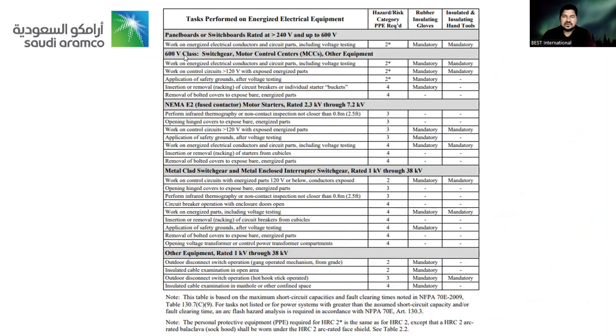Okay, so some further things about tasks performed on electrical equipment. There is a very straightforward criterion: if panel boards or switch boards are there, at 240 volts up to 600 volts, the hazard risk category is 2. Rubber gloves are mandatory, insulated hand tools are mandatory. In the same way, different areas are mentioned. For switchgear and motors, rubber insulated gloves are mandatory.